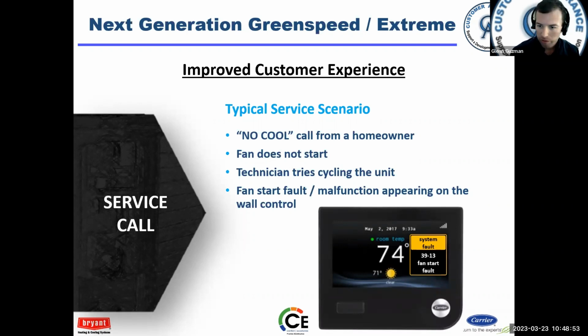If you're the dealer, and Mrs. Jones lives an hour away, I'm going to log in on the connected portal and see what other faults she has. It says fan start fault. I'm going to send the technician to the job with a condenser fan motor just in case, because he may need it. If I got fan faults, hopefully he doesn't need it, but if he does, he'll have it. That saves that back and forth and leaving the customer down.